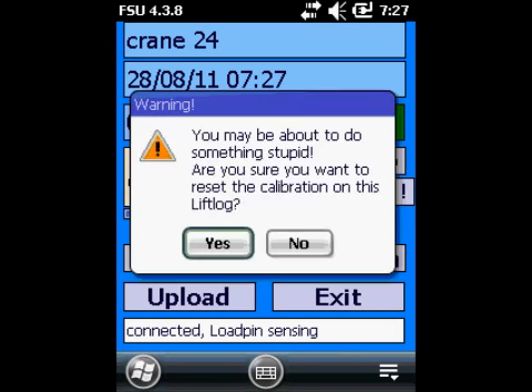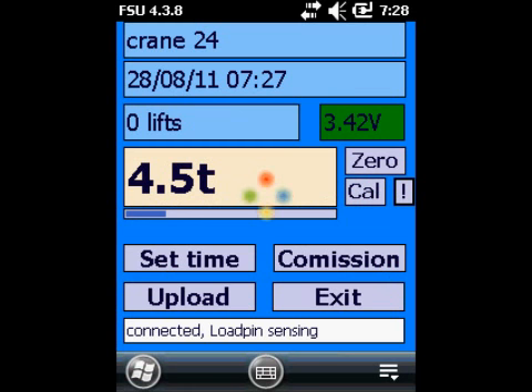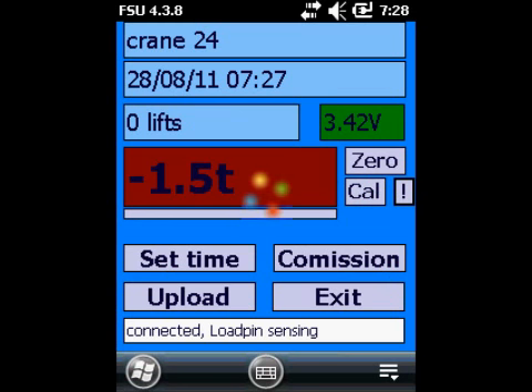If you ever get yourself into trouble, you can tap on that exclamation mark, and that will tell you you're about to do something stupid. This will erase the calibration on the lift log. So if it's not doing what you want it to do, you can just tap that exclamation mark button and hit yes. If you do, make sure you have a load handy to recalibrate the lift log with. If you don't have a load to be able to recalibrate the lift log, at this point you will erase the calibration and the load display will once again become meaningless. And you can see there that I've reset it and it's gone back to the factory defaults, which is pretty much the state it was in when we came in.